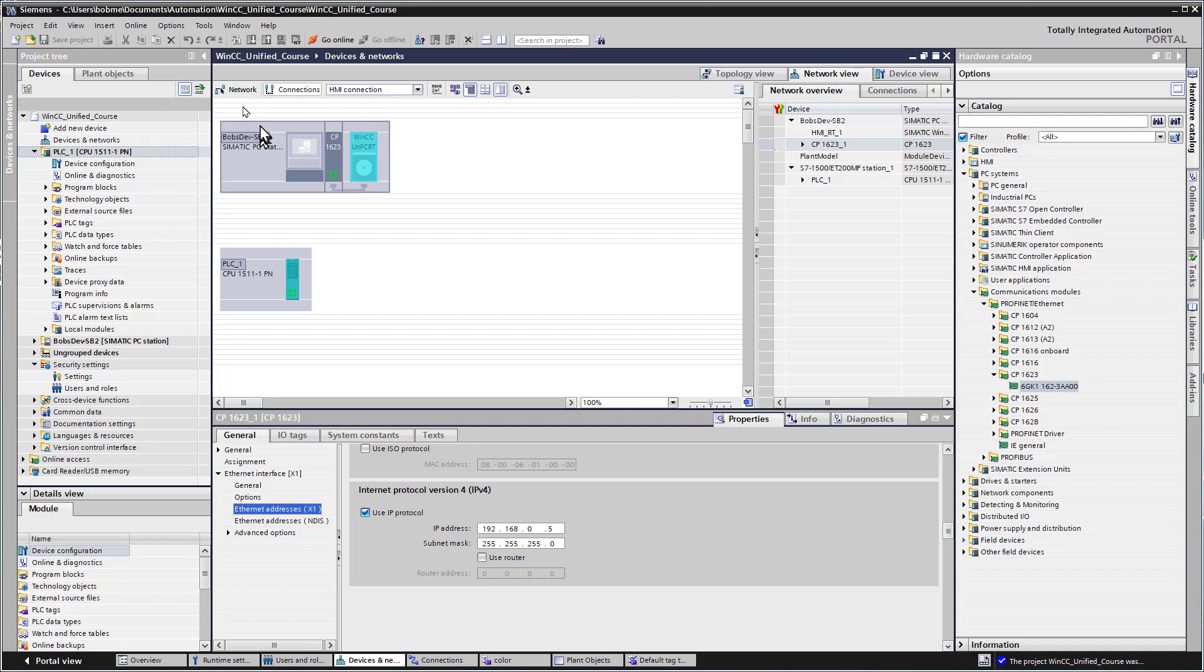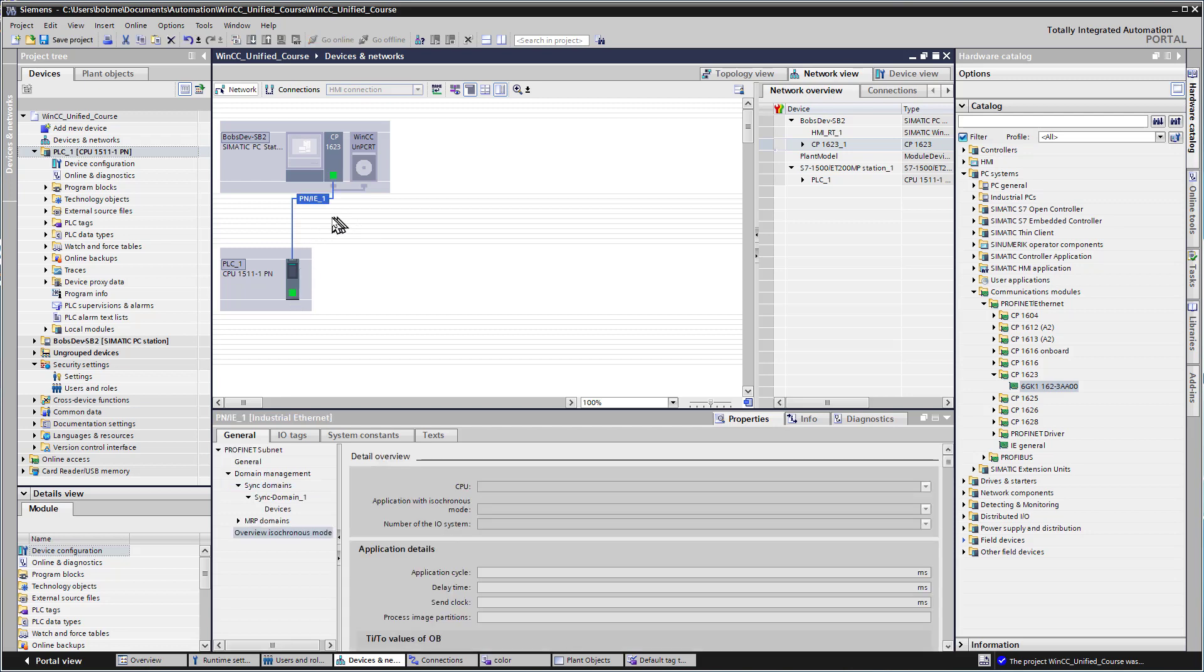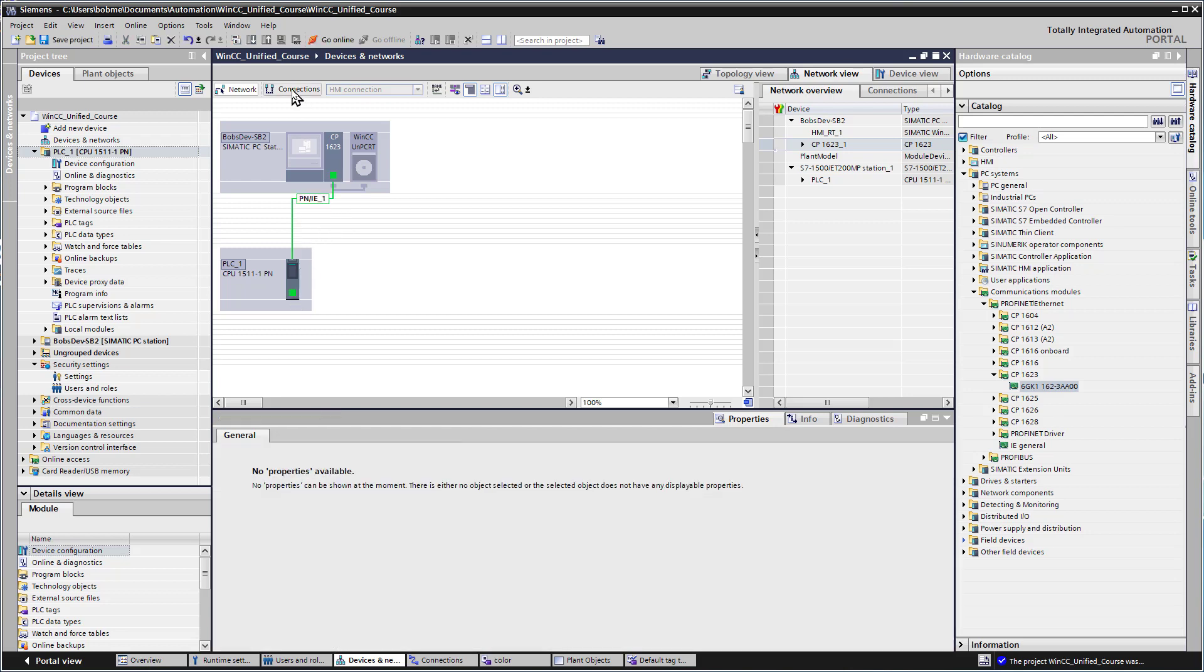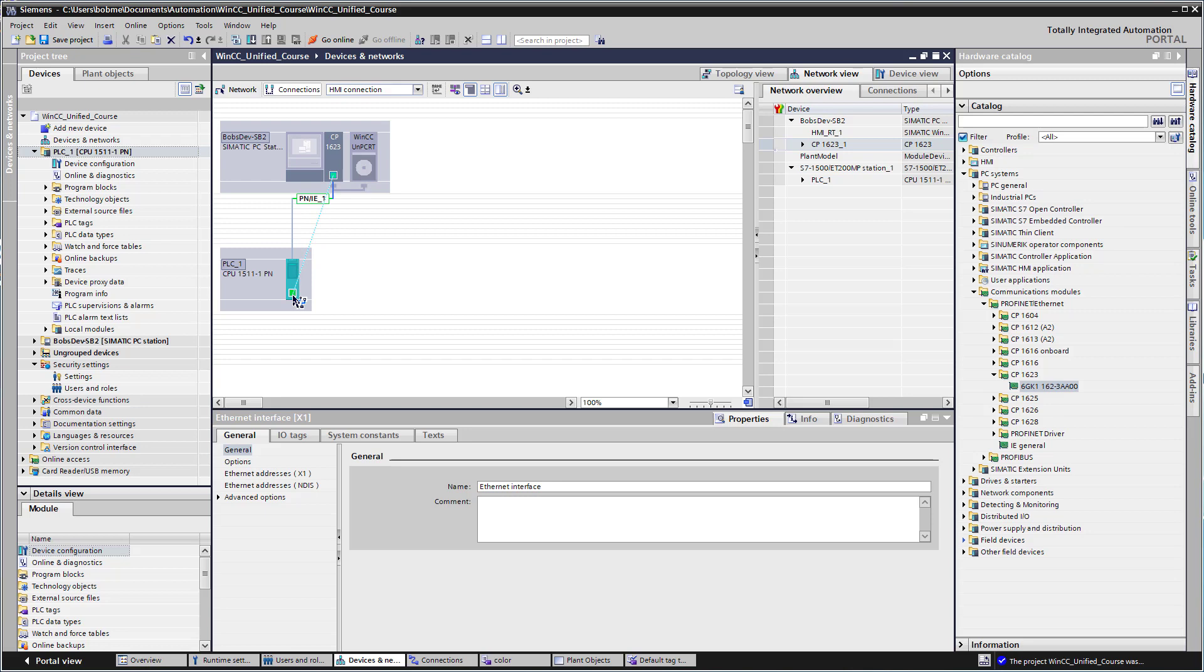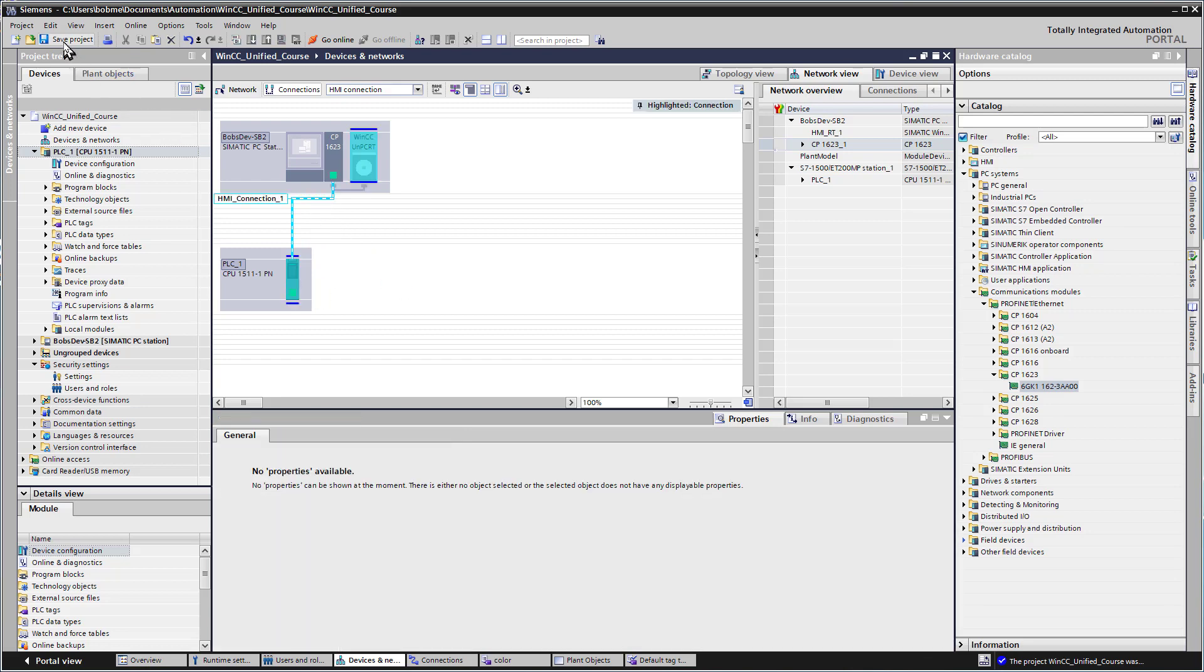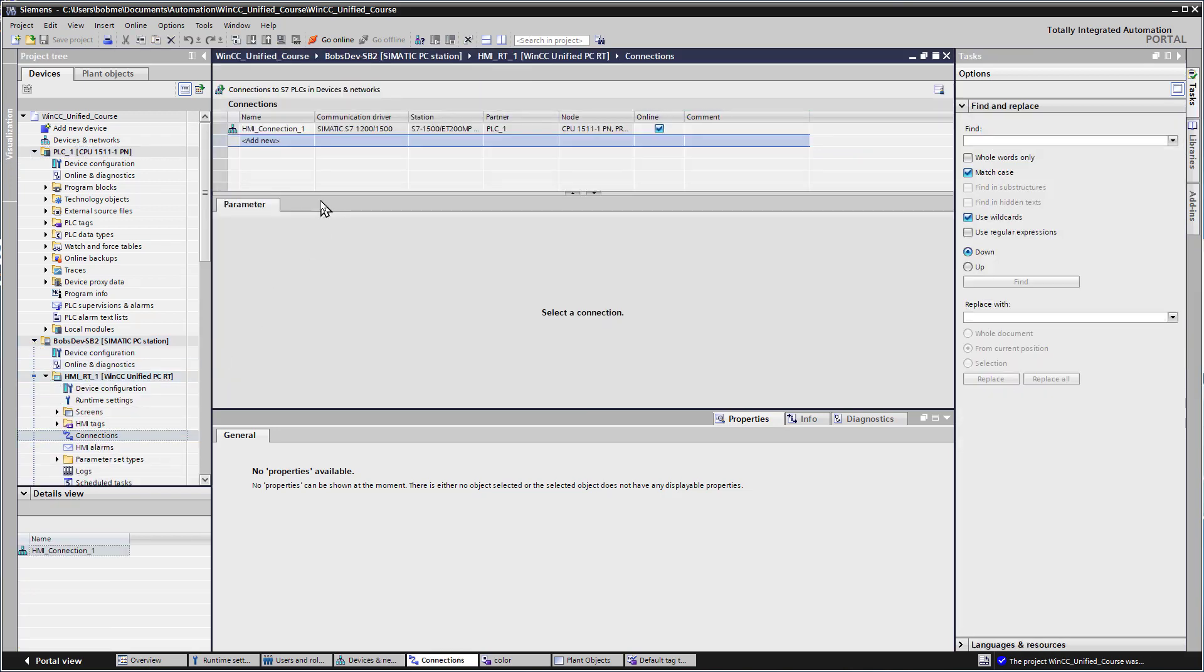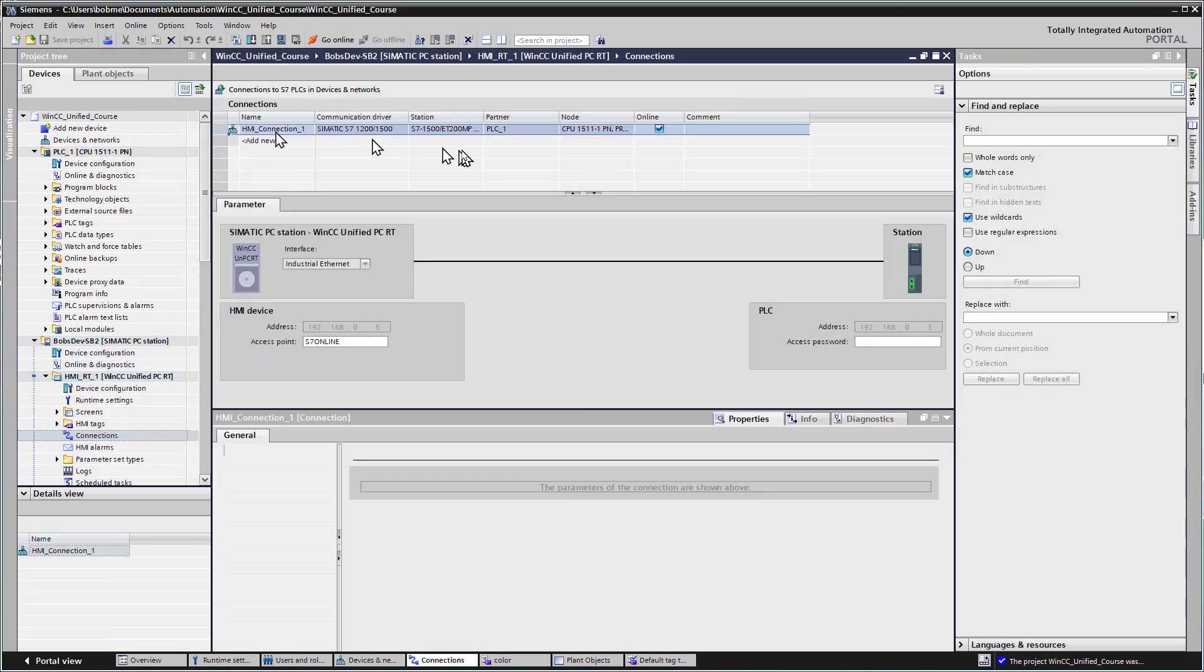We need to connect these up. Under Network, I'm going to drag these two together and it's going to create a network. Then I'll go to Connections and create an HMI connection. Going down to our runtime module under Connections, you'll see our connection there with our IP addresses.